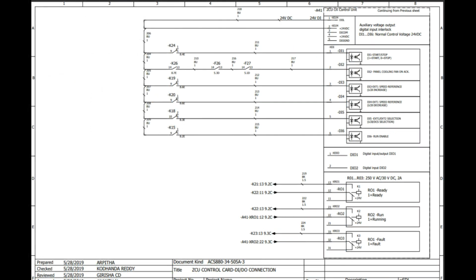On the top we can see the slot XD24. This slot is responsible for generating 24 volt internally. The control card will generate 24 volt, and it will feed the different digital inputs. The digital input slot you can see just below it, that is XDI, and there are a total of 6 digital inputs. We'll just see the first one, because digital inputs will vary according to the application. You can design it on your own: go to the parameters and select which digital input you want, as per the design and the process. For example, the first one is start stop, and the 24 volt has to go through K24. Once K24 is NC, normally closed, then 24 volt will come to this digital input DI1, and the drive will get the start command.